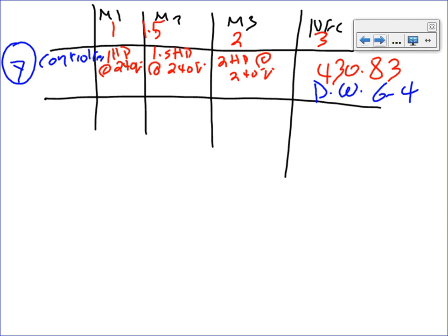Can you see it's 3-phase and single phase, and their voltages? I want you to go to the last 2 columns, which say single phase 230, 240. Can you see 230, 240? Okay, let's look at the horsepower of the first motor. 1 horsepower. What NEMA do I need for 1 horsepower? 00. So that would be NEMA 00. Now how are you going to read that? Check.